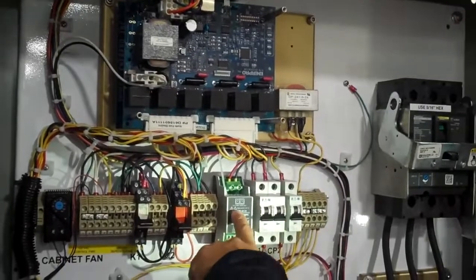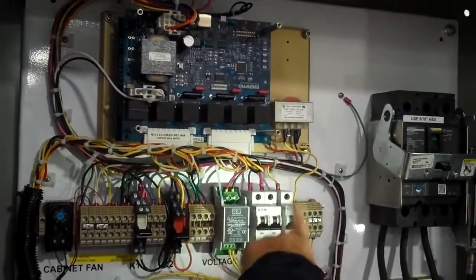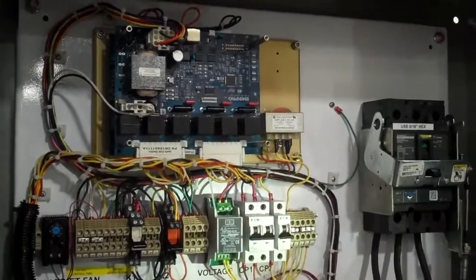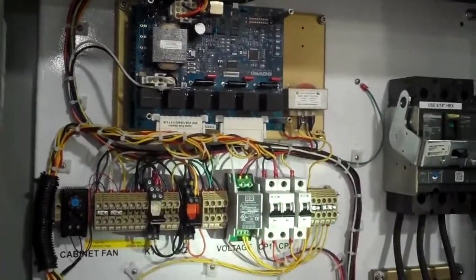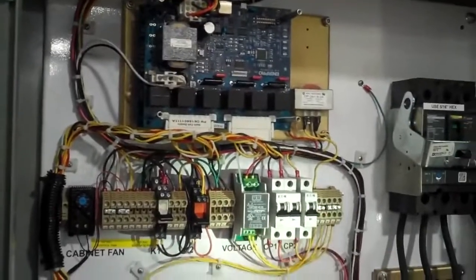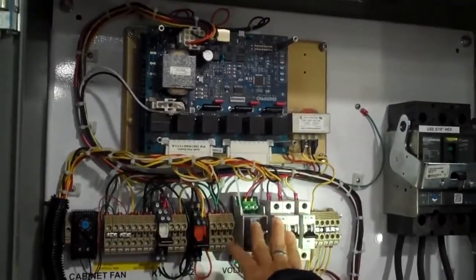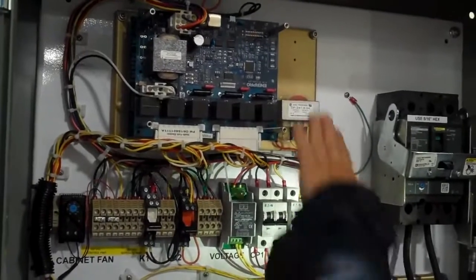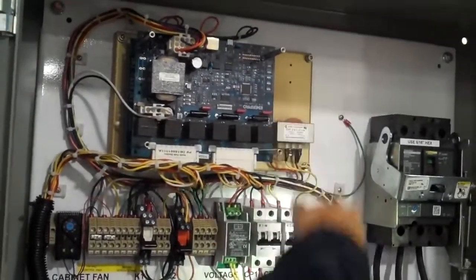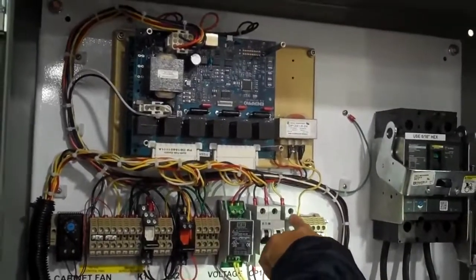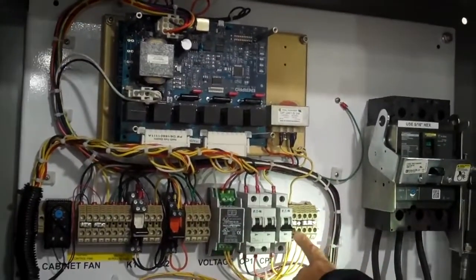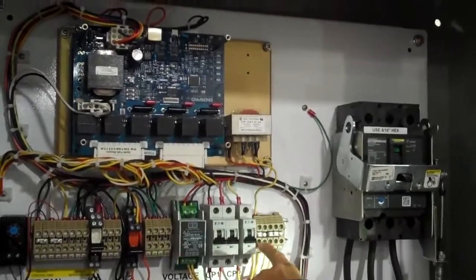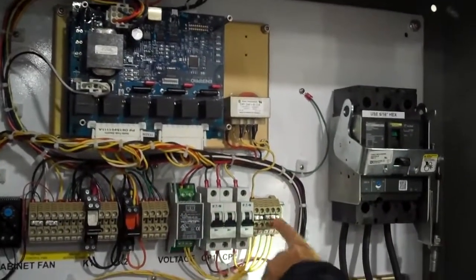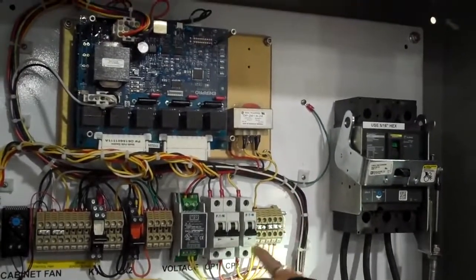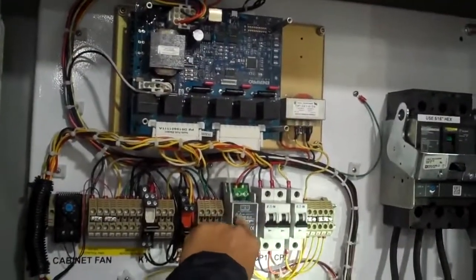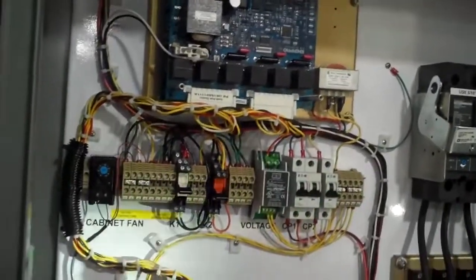We have the voltage transducer, which is picking up voltage from this transformer, and then it's monitoring the voltage across the bridge, and here we're picking up 4-20 proportional signals. We have the 2-pole breaker coming from the 208 into the 240 transformer, and this is the output, the 24 volts AC output out of that transformer. And here we see the position 16 and 17 jumper, and then the 18, 19, and 20 jumper. That's the 24 volts AC that gets distributed to the voltage transducer and also to the current transducer.